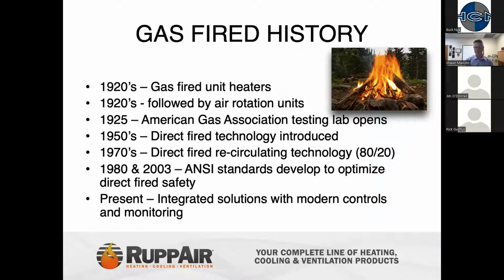In the upper right-hand corner, you can see that open flame burner. This is where the concept of direct fired technology comes into play, just that open flame. In the 1950s, direct fired units were first introduced into the industry. In the 70s, recirculating direct fired heaters came into the industry. We're going to explain more about those later. Then 1980 and 2003 were the pivot points for big changes in the governing bodies, the ANSI standards that looked at how direct fired is utilized and how it can be safe. And today, the biggest thing is integrating solutions with modern controls and monitoring, making sure that within all of this development of standards, we can control these buildings to meet the needs and requirements of the user.